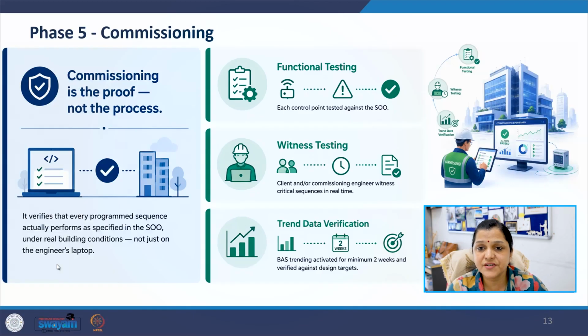Trend data verification is another important activity. The building automation system should collect operational data for at least 2 weeks. The data helps verify system stability, response time, and energy performance. Commissioning is essential, and it is the proof that the design intent has been achieved.